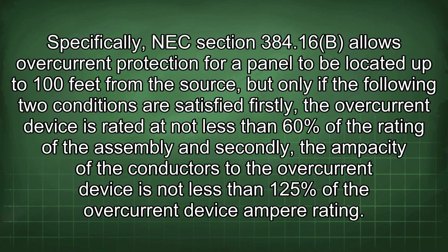Specifically, NEC Section 384.16b allows overcurrent protection for a panel to be located up to 100 feet from the source, but only if the following two conditions are satisfied. Firstly, the overcurrent device is rated at not less than 60% of the rating of the assembly, and secondly, the ampacity of the conductors to the overcurrent device is not less than 125% of the overcurrent device ampere rating.